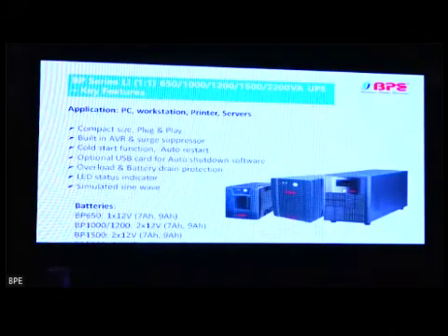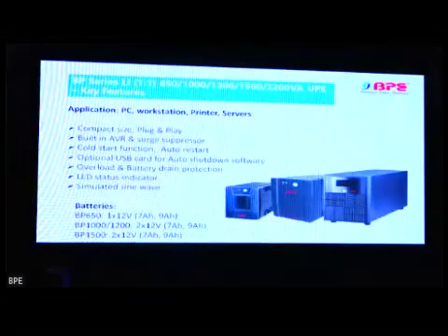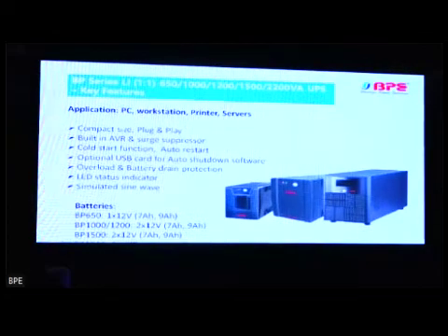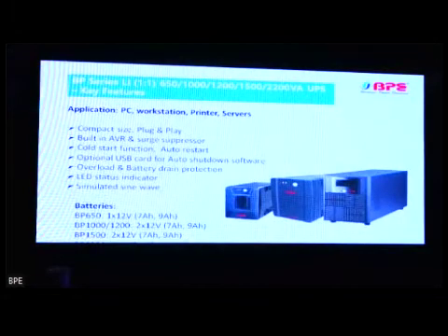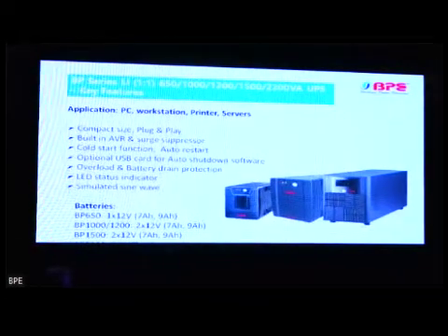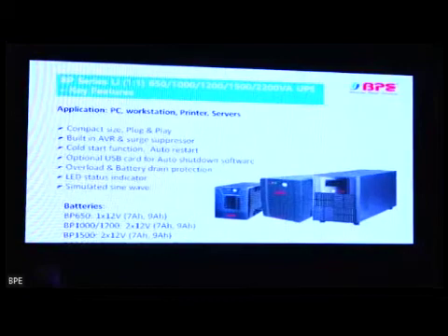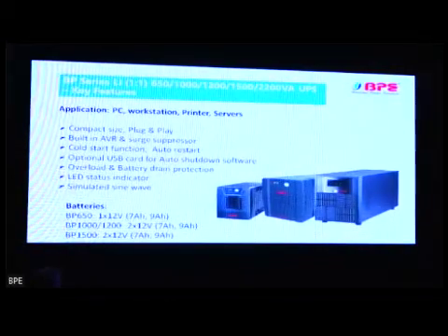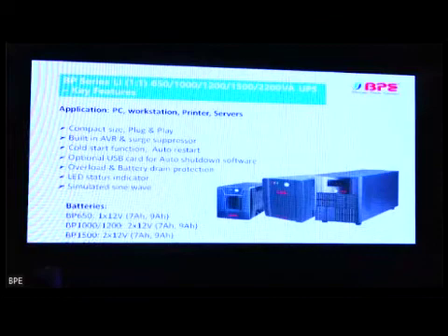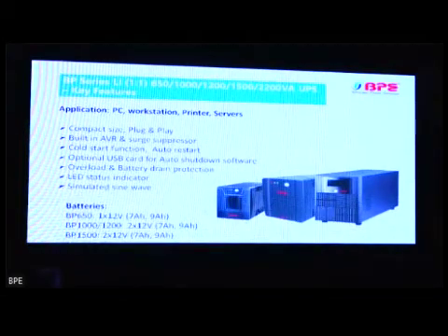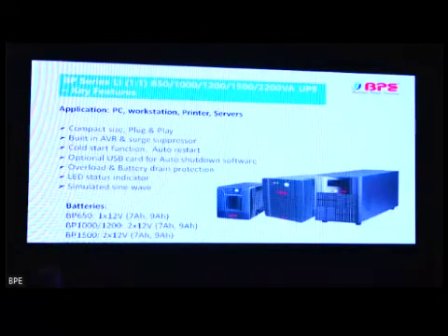It's compact in size, built-in AVR and surge suppressor in this. Cold start function is there. Cold start function is basically the UPS is able to start on battery only without AC connection. Then we have optional USB card for auto shutdown software, overload and battery drain protection, LED status indicator, and the provision for 650 VA is a single battery and 1000 and 1500 VA with the two battery sets.